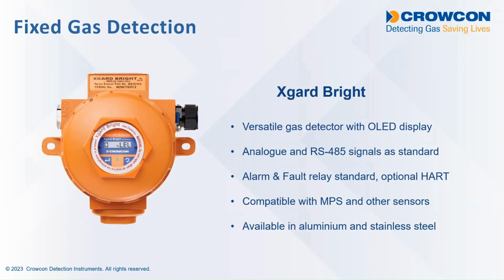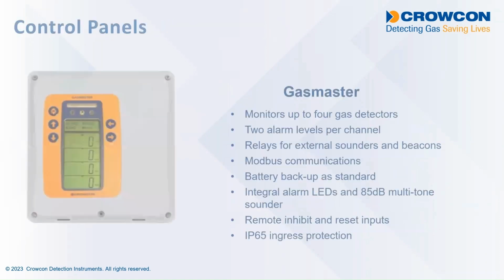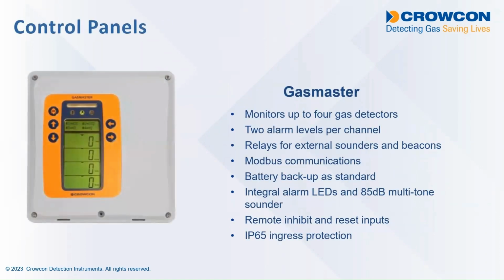Stainless steel is important because in a brewing environment, the carbon dioxide laden environment is quite corrosive, so we wouldn't recommend aluminium. That's why we have the 316 stainless steel version available. And then quite often our Xgard Bright detectors are connected to a control panel such as Gas Master. So the Gas Master would be outside of the area where the gas might be, and the Gas Master does the job of displaying the gas concentrations from up to 4 gas detectors.